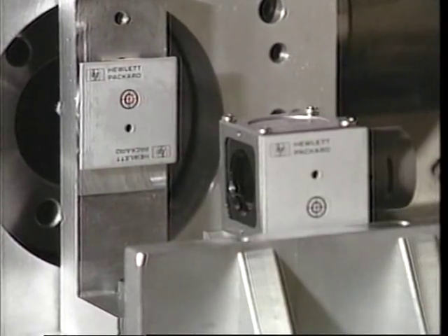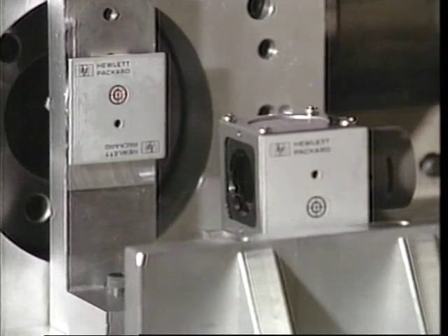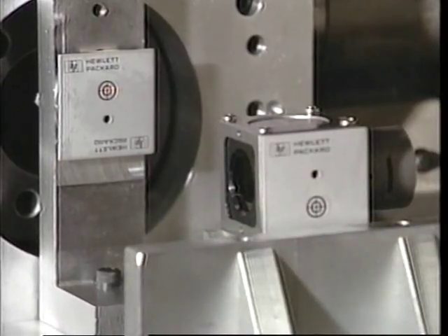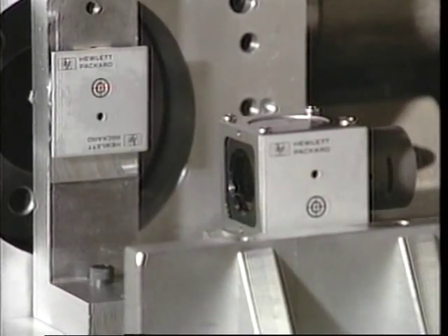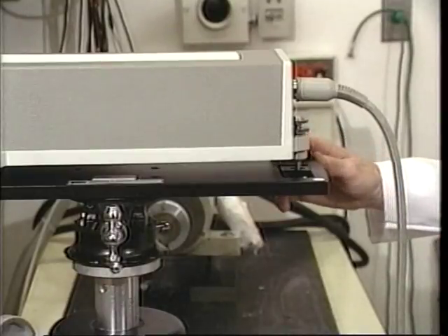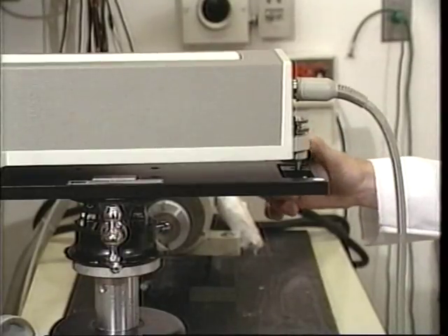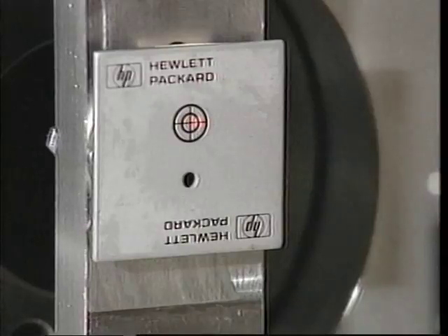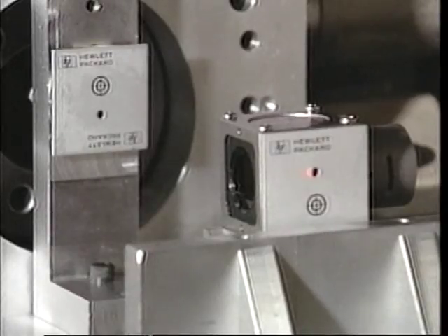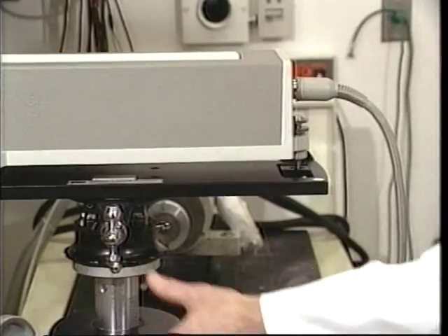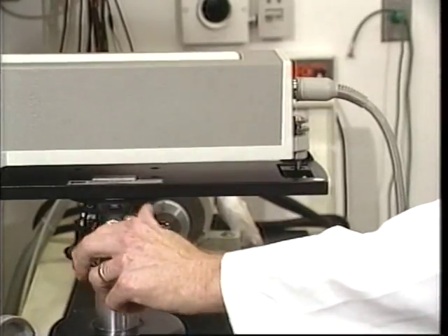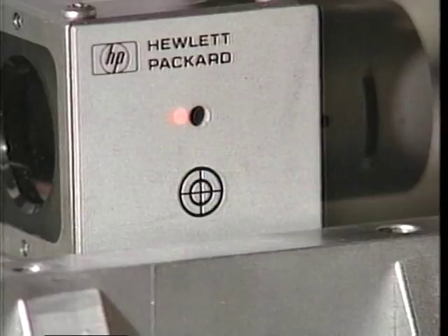Gradually move the retroreflector away from the interferometer until the beam has nearly moved off the retroreflector's target. Rotate the laser head horizontally and vertically to move the beam back toward the target's crosshairs. During this process, the beam will probably become partially blocked by the interferometer target. Now horizontally and vertically translate the laser head until the beam again passes through the hole in the interferometer's target.